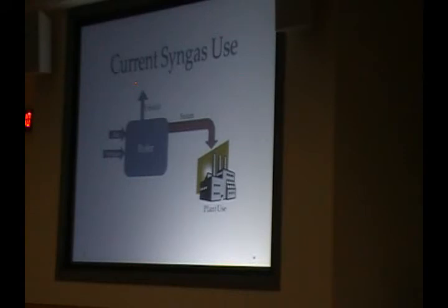I noticed the chemistry in the boiler. I'm not the foremost expert, but there's a lot of chemicals they're putting in there to maintain the boiler, to keep it from corroding and stuff like that. One facility I work at actually feeds two plants, and both plants run on slightly different chemistry for dyeing of the carpet. So we have to be mindful of the chemicals we have in there and the levels, because they will affect the actual dyeing of the carpet and throw off the colors and shades and how the dye bleeds into the fibers.